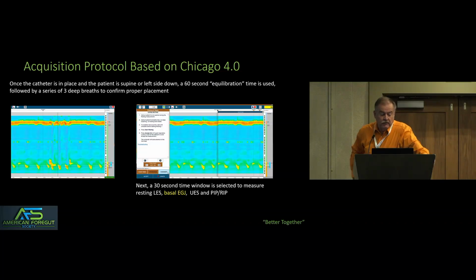And to be sure you're in the proper position, we then ask them to take a series of deep breaths, and look at the dynamic portion of the crus of the diaphragm when we ask the patient to take a deep breath versus a shallow breath. Now you've got your position exactly where you want. You set your anatomic position bars, UES, LES, and now you're ready for part 2. The next step is you're going to take a 30-second time window, and you're going to measure resting LES, and for Chicago 4, resting EGJ, the UES, and the PIP-RIP, which is a pressure inversion point, or depending on your training, the respiratory inversion point, at which you leave the abdomen and enter the thoracic cavity.